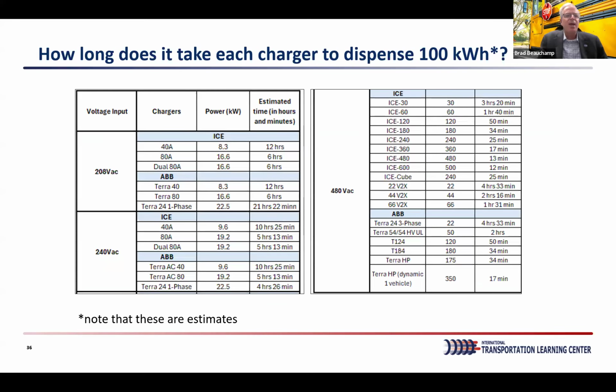There are chargers to look at. Even in AC charging, I mentioned 240 volt AC — those same chargers often operate on 208 volt, which is part of a 3-phase system. The difference is there are charts and times that accommodate this, and the rate of time to put 100 kilowatt-hours into a battery is displayed here. So for a 100 kilowatt-hour battery, this gives you relative charge times. You need to be familiar with that as you're planning your charging, both for how long it's going to take, and if it's overnight it's usually not a challenge. If you have to take note of demand charges, you might have to consider alternate methods. But there are chargers for every level here.